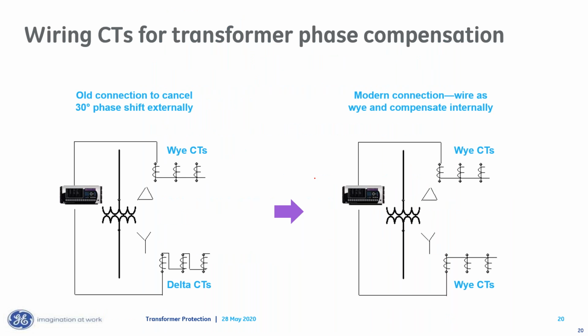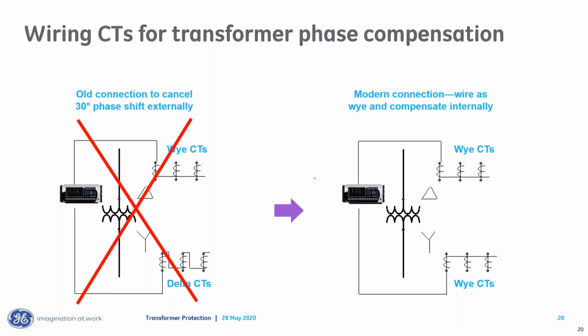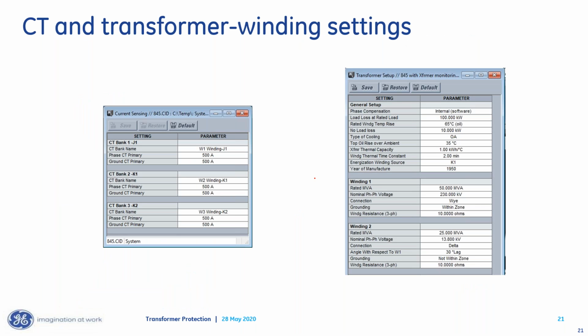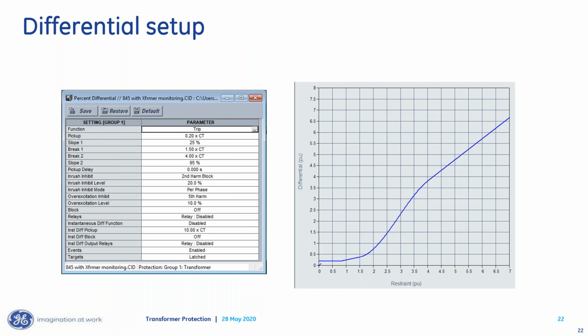Now, the way that we used to take care of compensation back in the electromechanical relay days is we would wire the Y winding CTs in delta, the delta winding CTs in Y. We don't have to do that anymore. We can let the relay take care of compensation with the settings. So here are those same settings that I mentioned earlier in the 8 series versus the UR that I talked about earlier. The main thing here is that we're going to set this at minus 30 degree lag, and that's the angle with respect to setting. Okay, differential 8 series, same way.